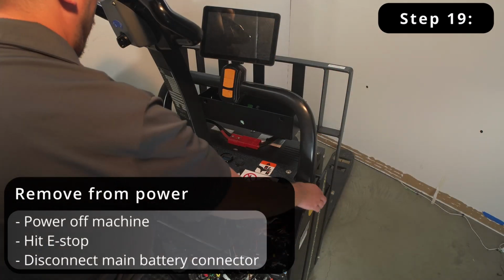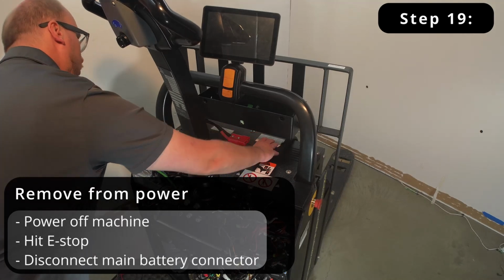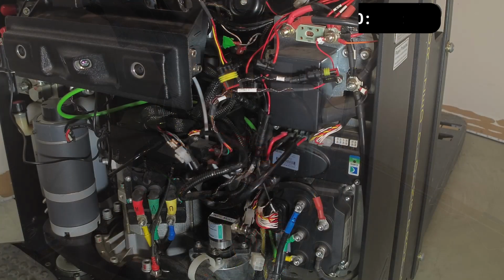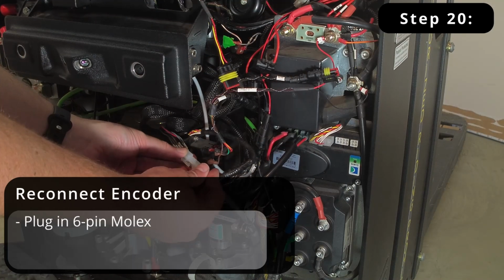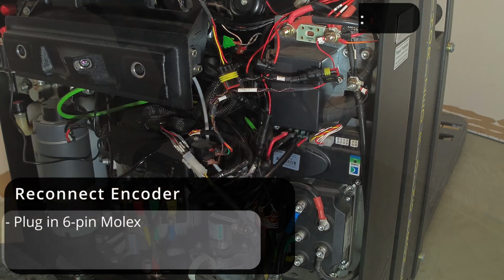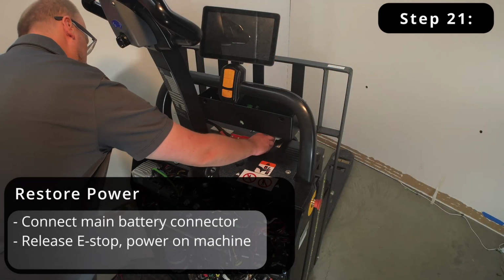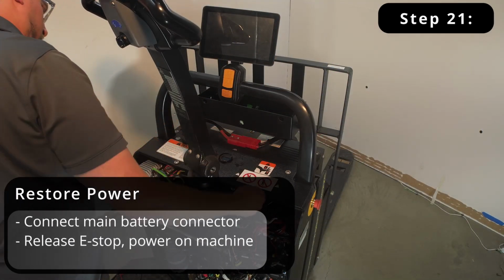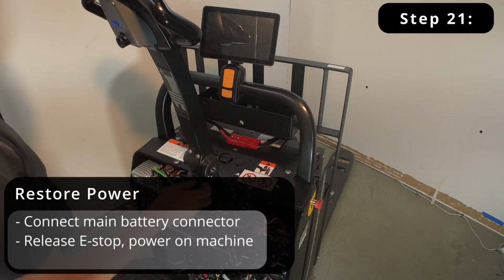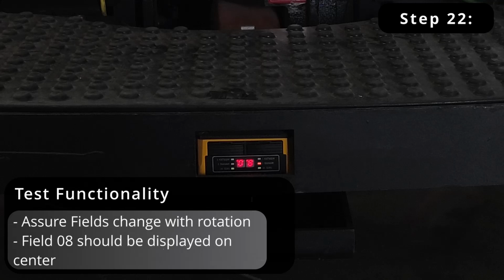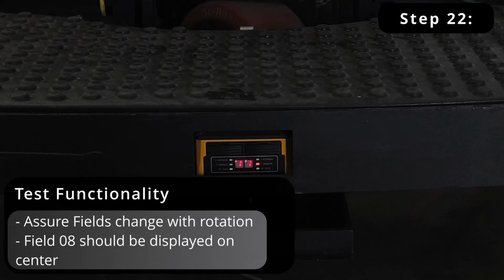Power off the machine again. Turn the key switch off, press the emergency stop, and disconnect the main battery connector. Reconnect the 6-pin Molex from the encoder to the machine. Reconnect the main battery connector, release the emergency stop, and power on the machine. Test the robot to ensure proper operation.